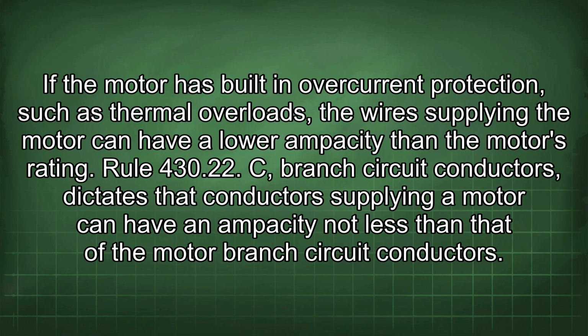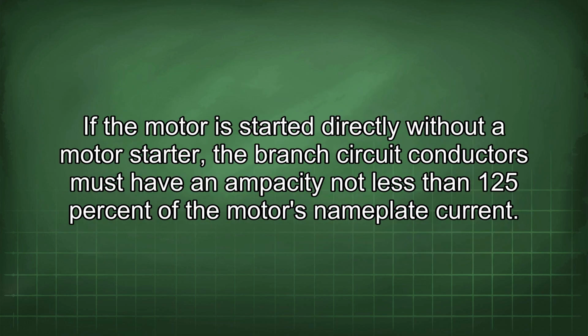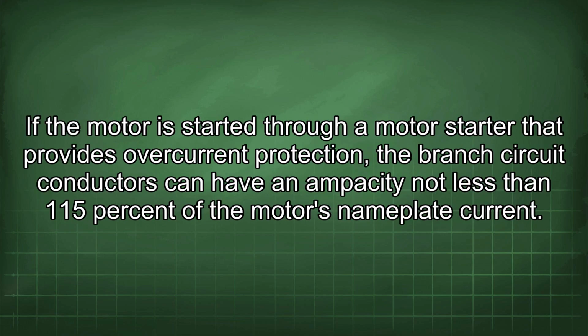Rule 430.22 C, Branch circuit conductors, dictates that conductors supplying a motor can have an ampacity not less than that of the motor branch circuit conductors. If the motor is started directly without a motor starter, the branch circuit conductors must have an ampacity not less than 125% of the motor's nameplate current. If the motor is started through a motor starter that provides overcurrent protection, the branch circuit conductors can have an ampacity not less than 115% of the motor's nameplate current.